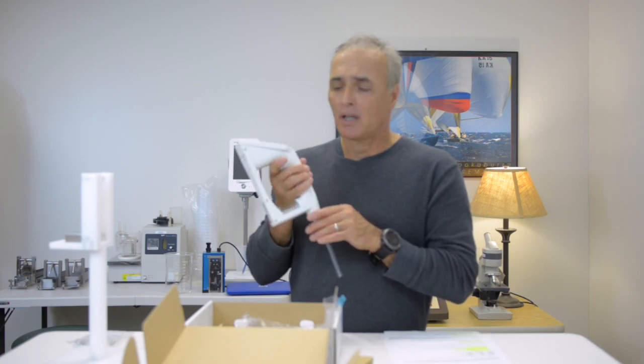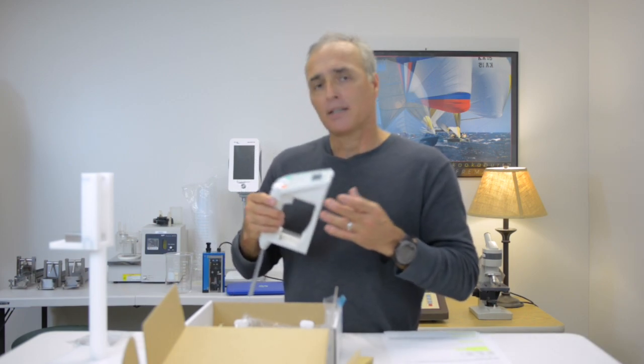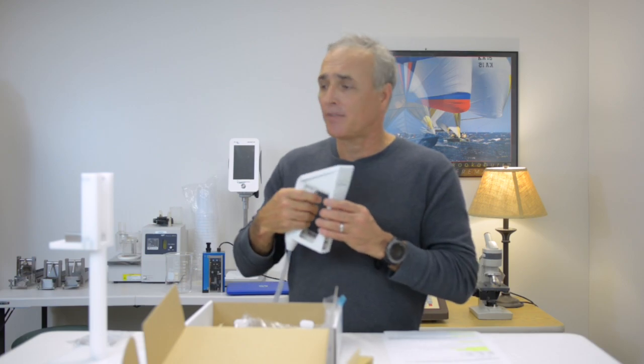There's a lot of functionality with this unit. It can take an instrument and make it good for just one application, but this instrument actually does a lot. It has a number of measurement capabilities — obviously density and specific gravity, but you can also do temperature-compensated specific gravity and density, where you preset a temperature and it handles the compensation. Beyond that, you've got API degree, Brix concentration, which is a popular application, alcohol concentrations, sulfuric acid concentrations, Baumé, Plato, and proof. You can also come up with any custom concentration methods you want to use the meter for.